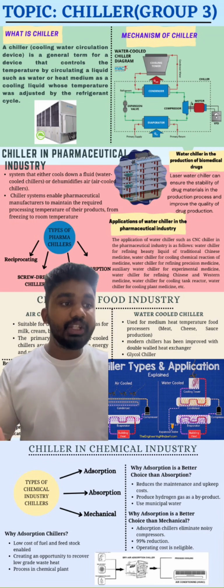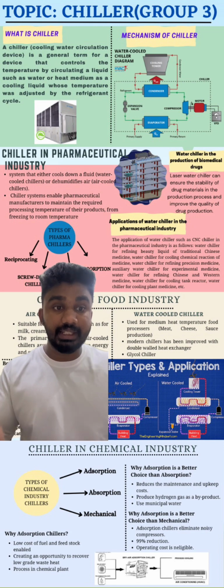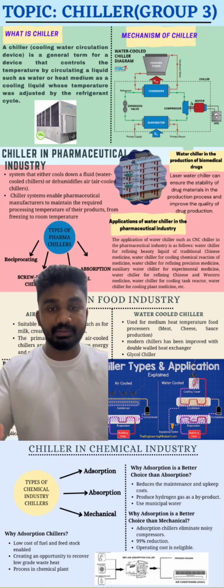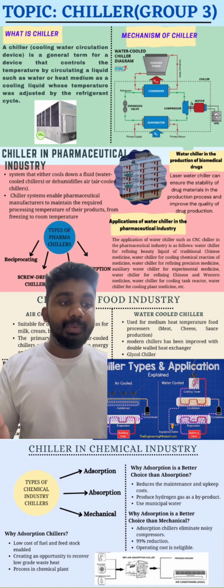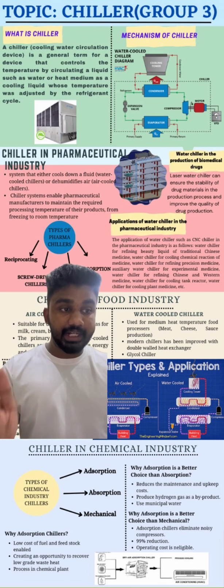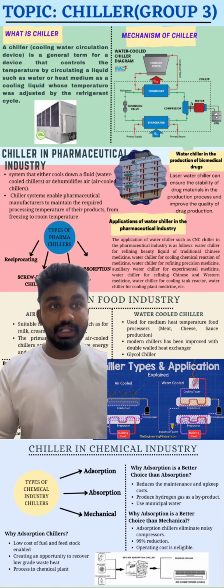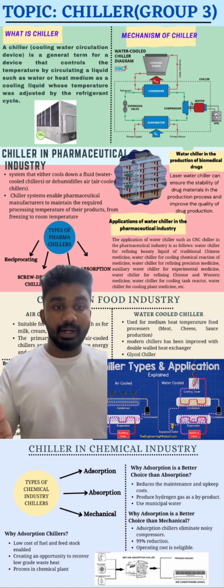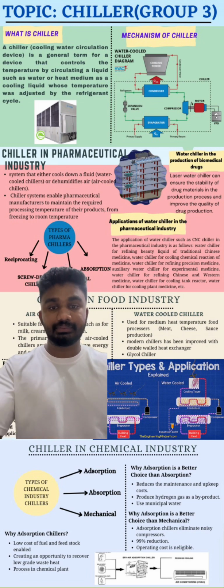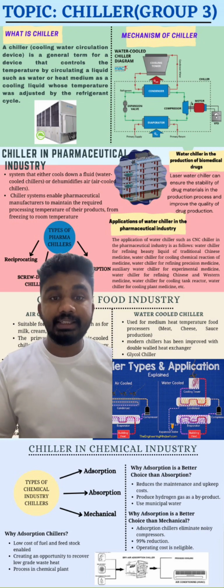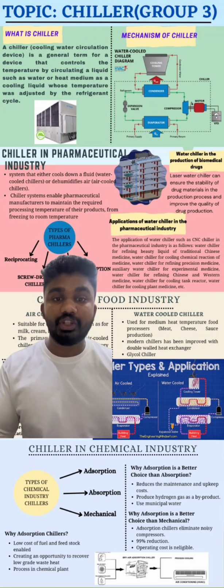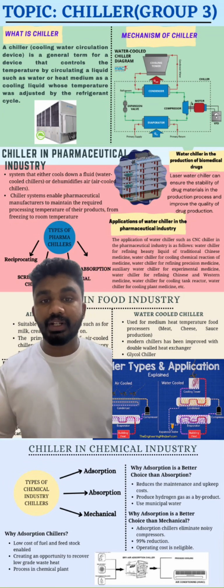Adsorption chillers will provide a 99% reduction in the chiller's electrical usage. The operating cost is negligible for an adsorption chiller. Meanwhile, the operating cost for a mechanical chiller is very high. So yes, these are the reasons why I chose adsorption chiller instead of absorption and mechanical chillers.